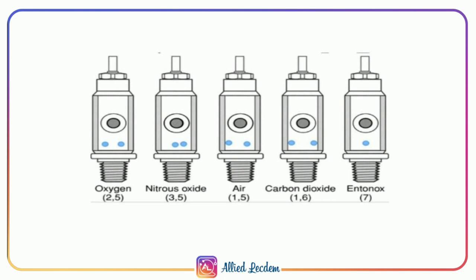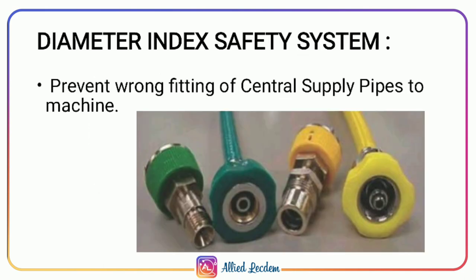While the pin index safety system prevents wrong fitting of cylinders to the machine, the diameter index safety system prevents wrong fitting of centrally supplied pipes to the machine.